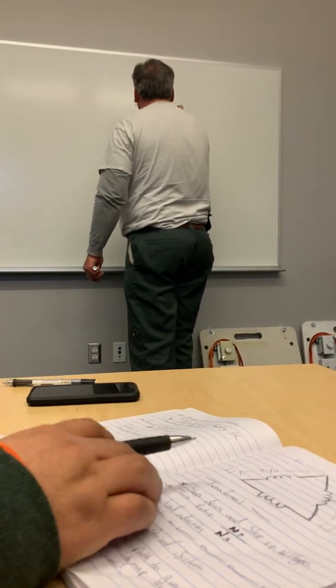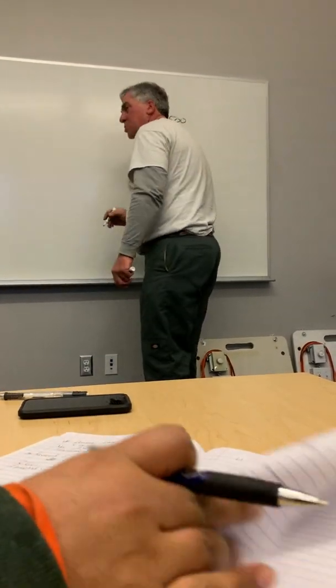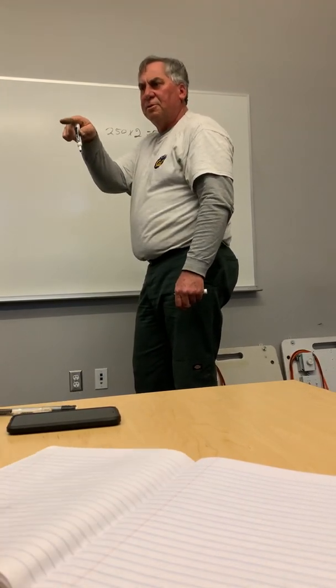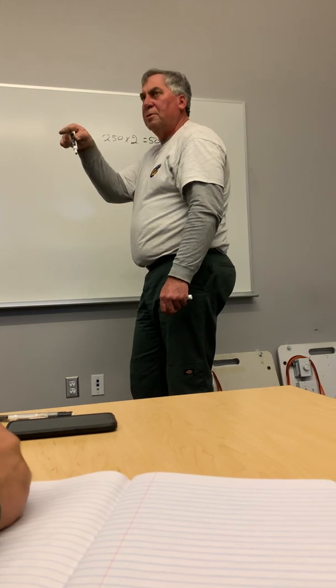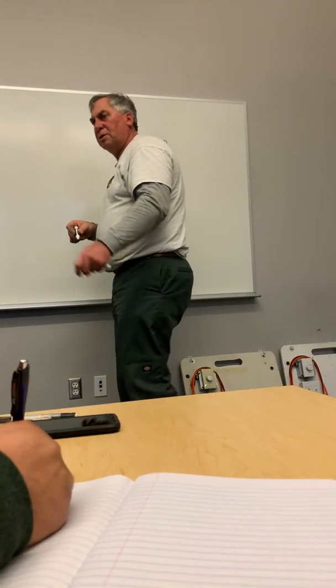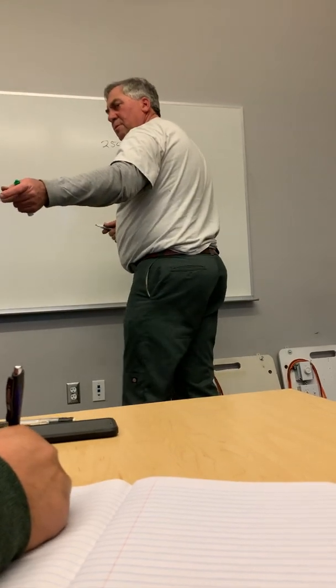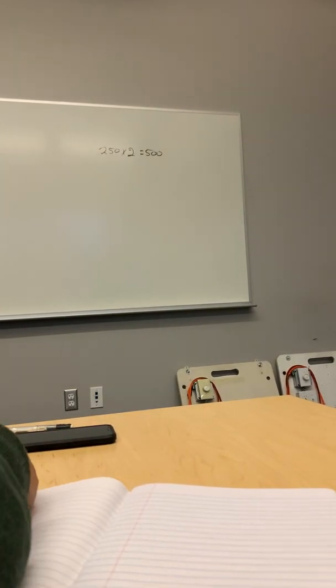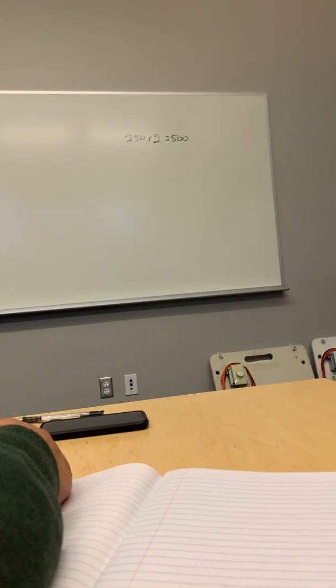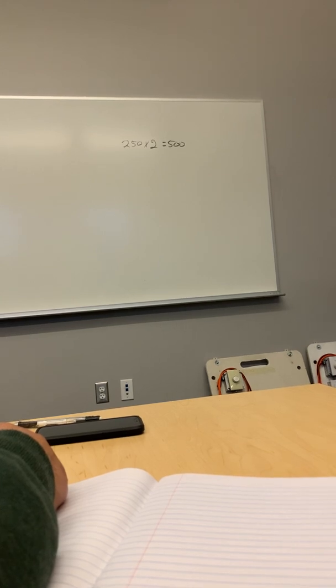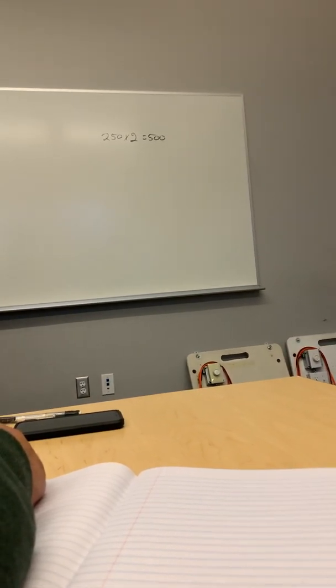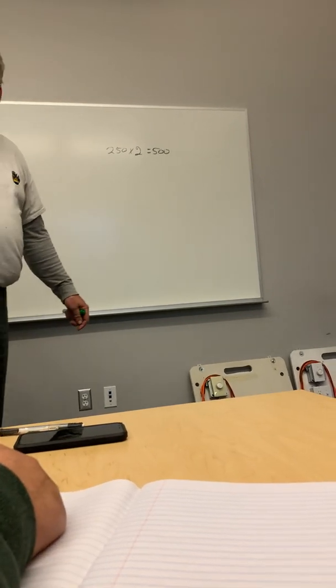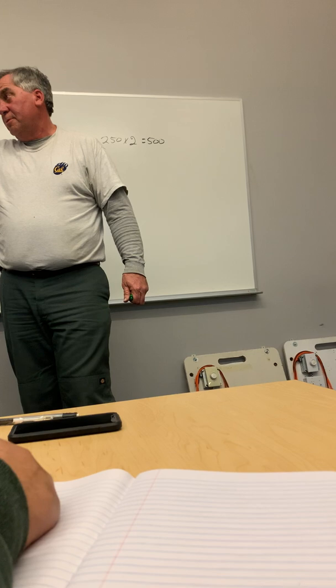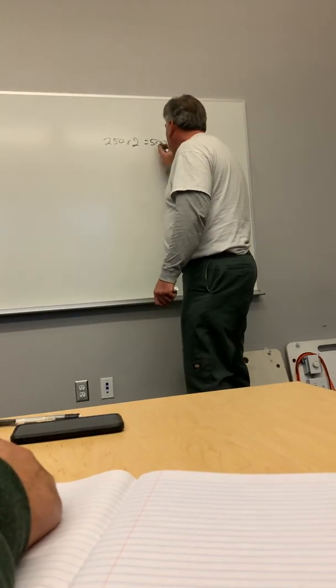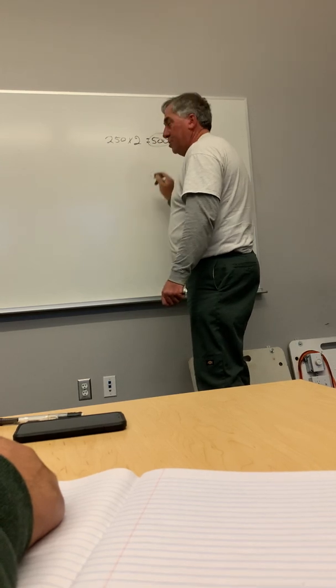So we have 250 times 2, 500. So is it 250.66 that has the size of the conductors that we're going to test on? The 250.66 tells us the size of the conductor. And I can't see without my glasses, so you gotta tell me. For 500, we want to run a number 2 copper to be our ground for this, right? And this is on the secondary. Yes. So we want to run number 2 copper because we have to take the total amount, right?